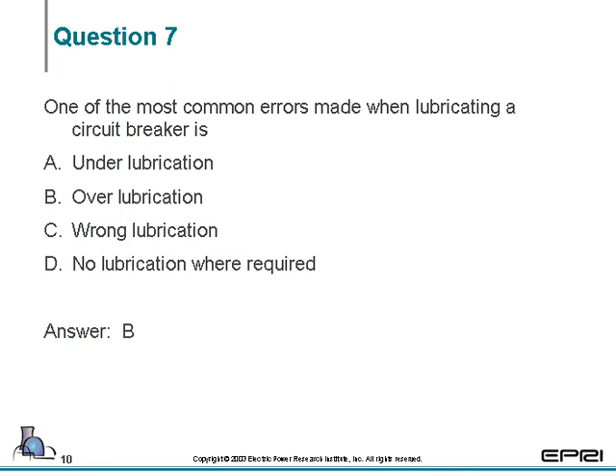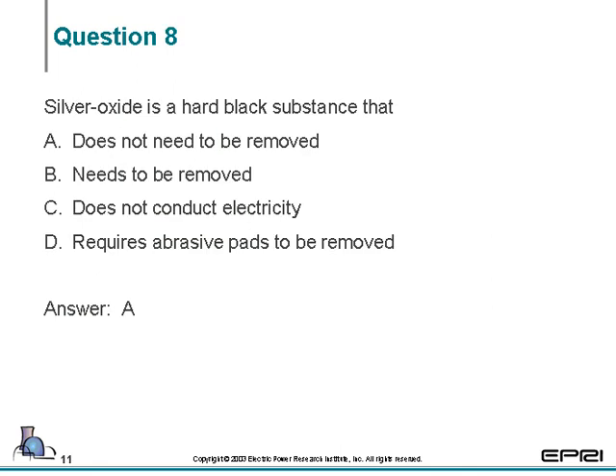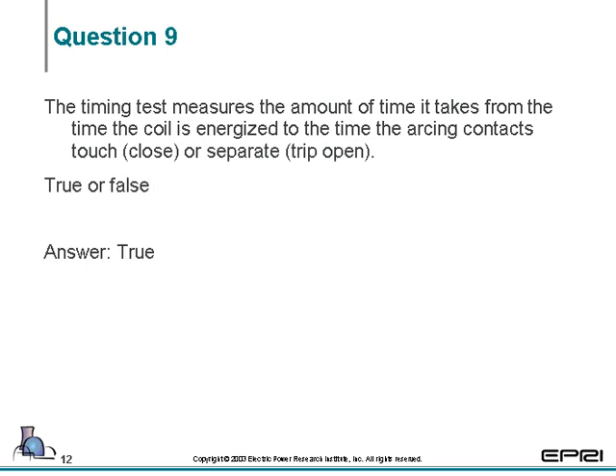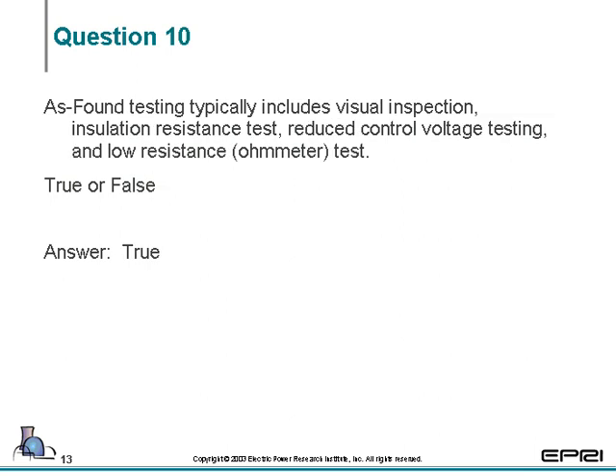So, question 7. One of the most common errors made when lubricating a circuit breaker is B, over-lubrication. We mentioned that several times in session 1 and covered it again in this session. Question 8, silver oxide is a hard black substance that A, does not need to be removed. The answer is A. It is as good or better a conductor than silver or copper. Question 9, the timing test measures the amount of time it takes from the time the coil is energized to the time the arcing contacts touch on close or separate on opening. True or false? The answer is true. Question 10, last question. As-found testing typically includes visual inspection, insulation resistance test, reduced control voltage testing, and low resistance ohm meter test. Again, that is true.